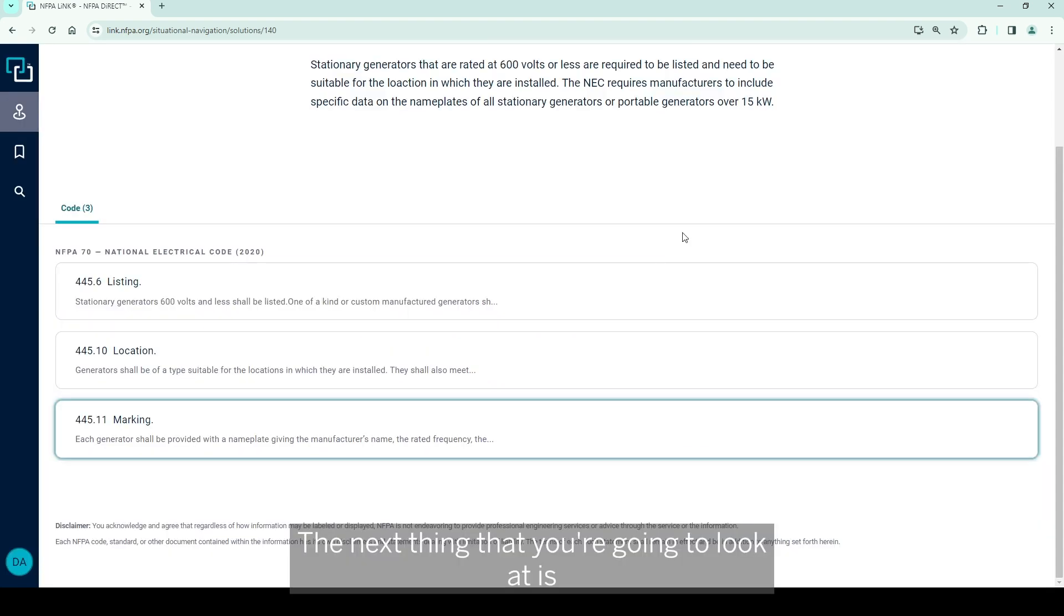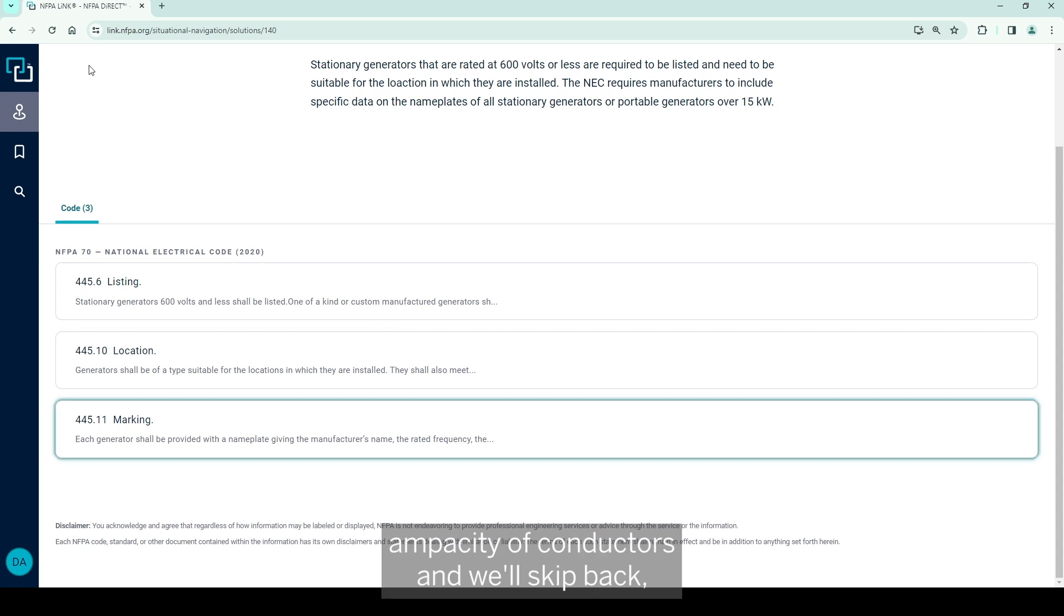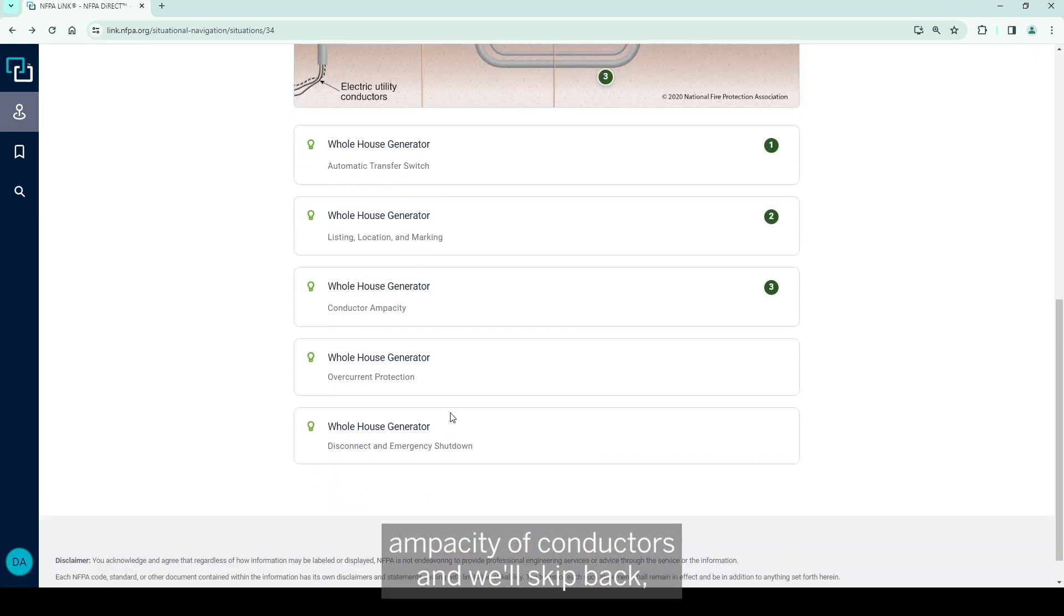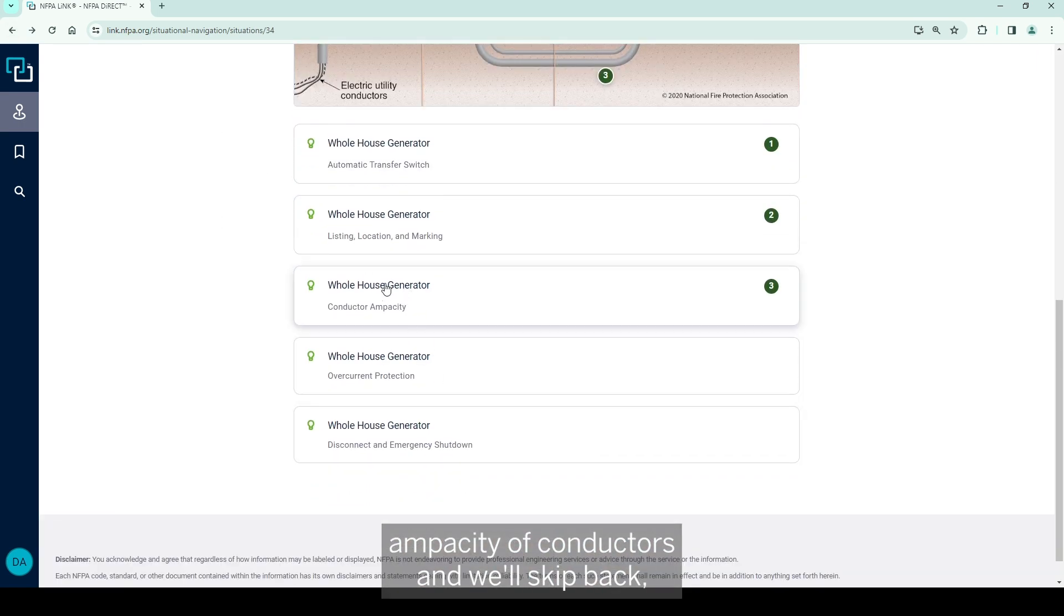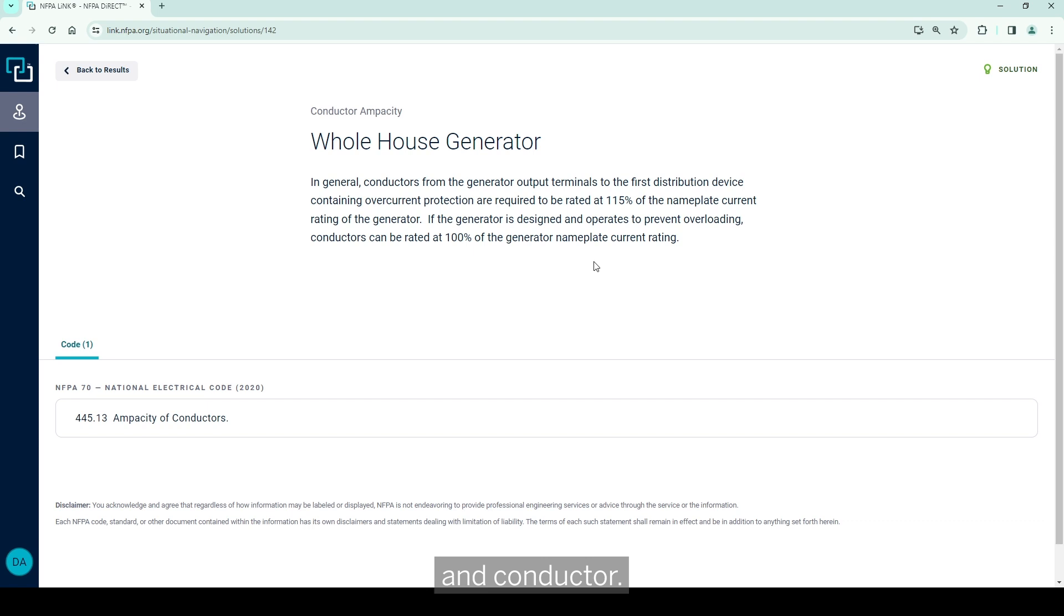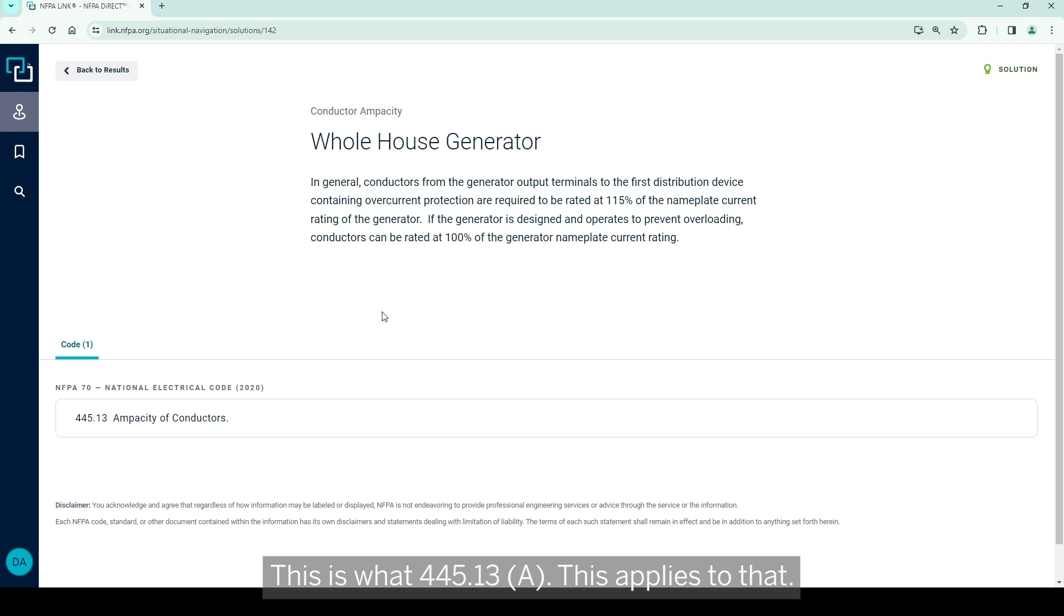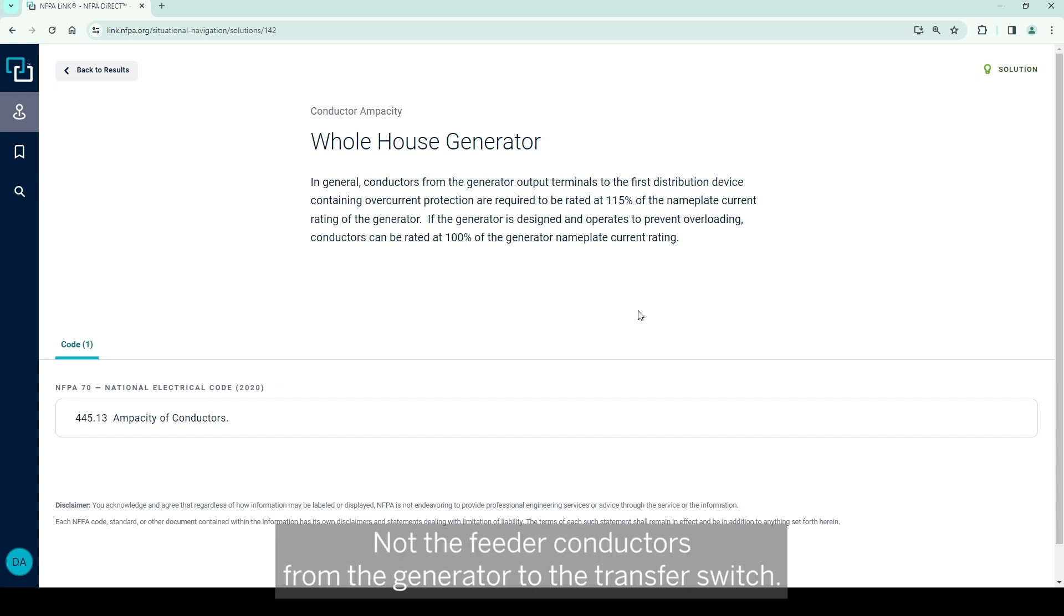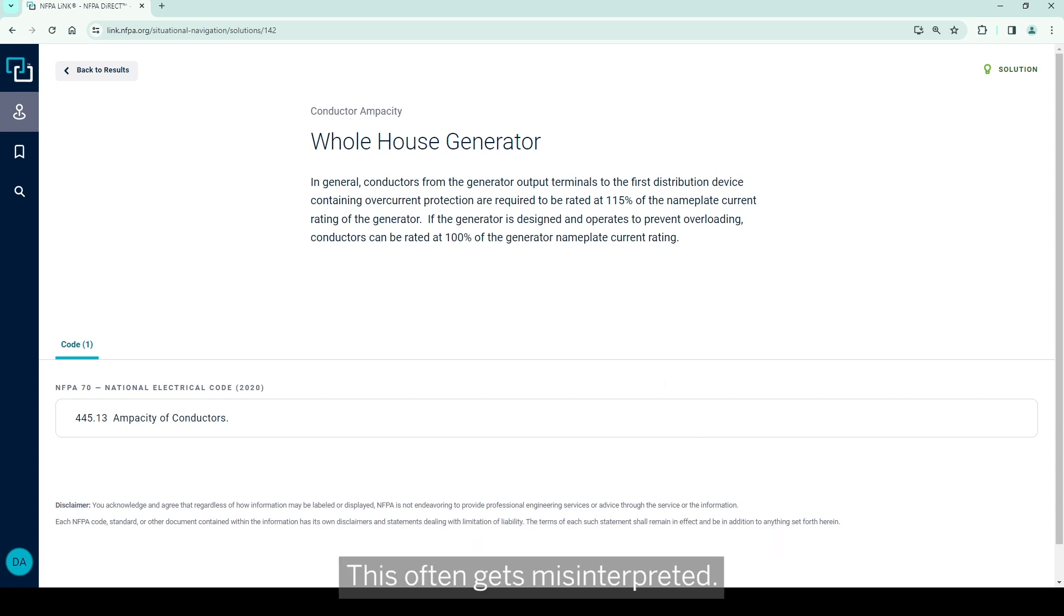The next thing that you're going to look at is the ampacity of conductors. This is for the generator conductors, and this is 445.13A. This applies to that, not the feeder conductors from the generator to the transfer switch. This often gets misinterpreted.